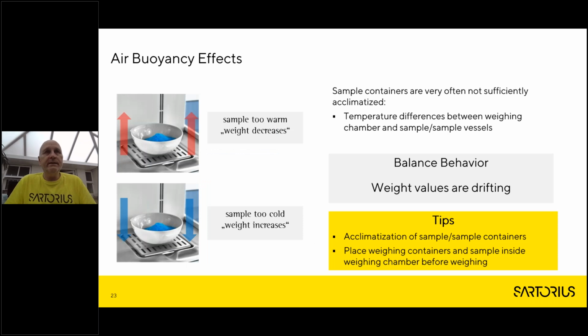Let's now talk about air buoyancy. If we think about it, air has a mass and therefore we have to think about how this mass interacts with our weighing process. If your balance is drifting, it could possibly be an air buoyancy effect. Let's say, for example, your sample is too hot and hasn't stabilized. As it cools down, your weight will decrease. Opposite to this, if your sample is too cold and it warms up, your weight will appear to increase and not be stable. So what we should do here really is acclimatize our sample in the laboratory next to the balance, or even inside the weighing chamber, before we start the weighing process.